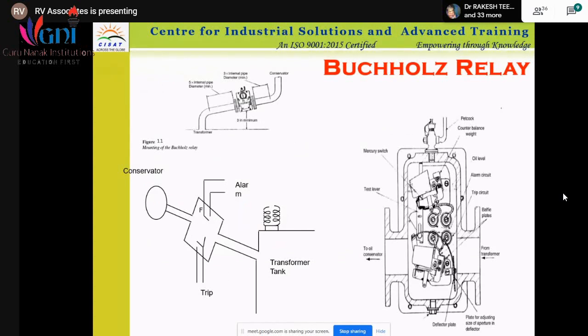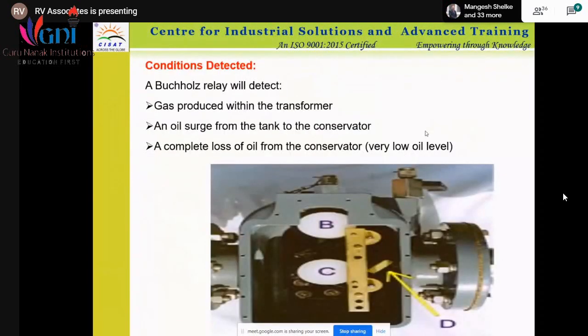Then we know how it is to be connected. There should be some angle between the conservator and the main transformer. So again, that engineering is there. Whoever the supplier of the transformer is, he will give you the exact idea of how that construction is done. What does it detect? It detects gas produced within the transformer. How is gas produced? Based on the temperature, 90-degree gas production will be different from 120-degree gas production. There will be ethane, methane, acetylene, and around 100 types of gases formed in the transformer based on the rise in temperature.